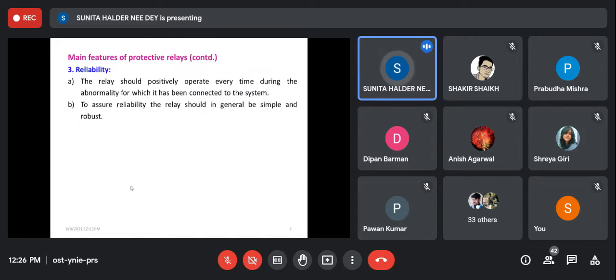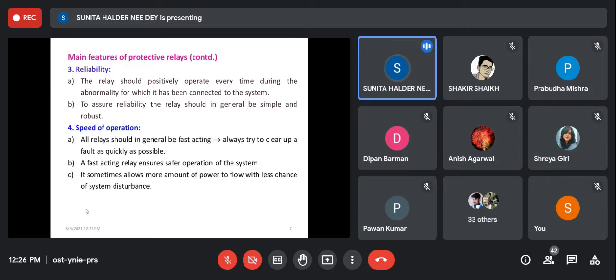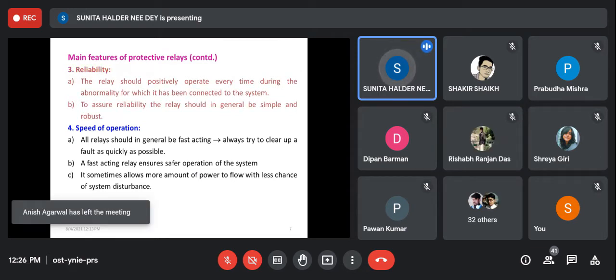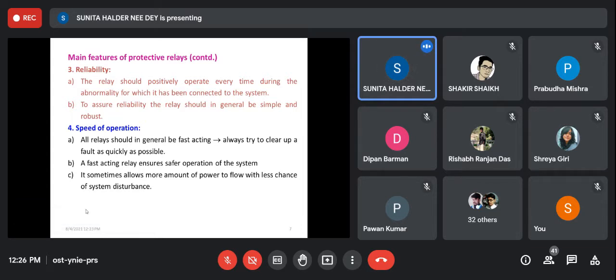Next is reliability. So what is reliability? Whenever we expect that a relay should operate, it should operate. Otherwise, its reliability will be threatened. Next is speed of operation. That means when there is a fault, when there is an abnormality, the relay should operate at the earliest. Okay. So always a fast acting relay is preferred.